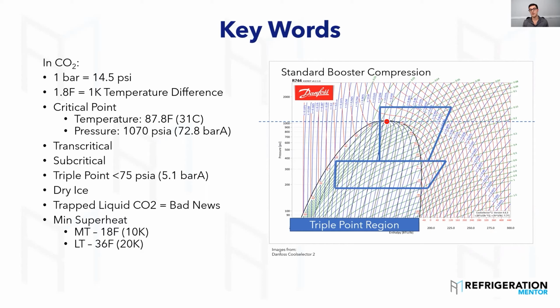And most of the compressor failures that I've seen with CO2 were due to liquid washing the bearings and washing the oil out. Anyone have experience with that in the field? Have you replaced any compressors that failed because of superheat?